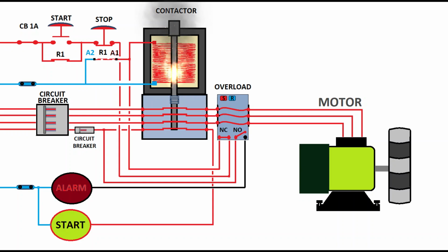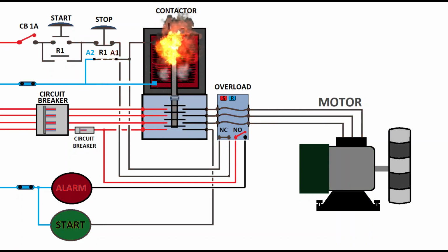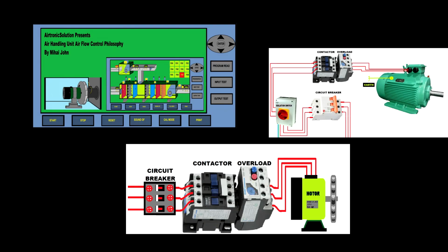Also, you have to understand how the control works. You see, this is a contactor failure, and obviously it will affect the power circuit, but there's nothing wrong with the motor or the power circuit. In this case, it's just the contactor. I saw an electrician who changed the motor for this one. That's quite crazy.